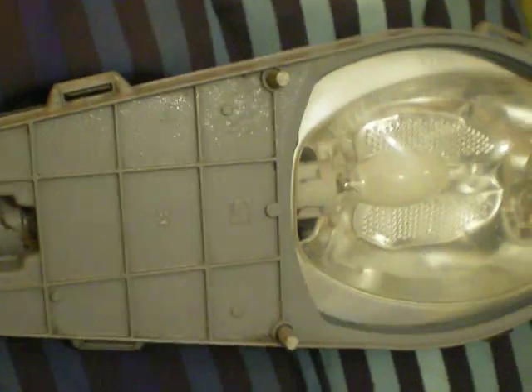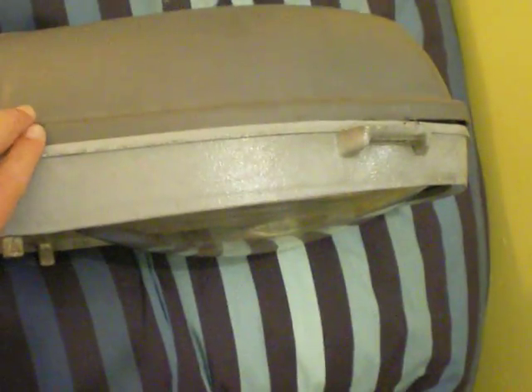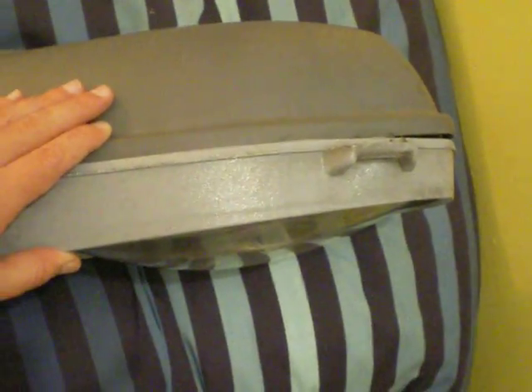So to change the bulb, you don't have to turn the fitting around. The engineers just remove the roof — the top bit. This is where the actual post would go in. You have a set of allen keys, undo these screws, put the metal rod through there, then do them up nice and tight and it's fixed. It's a sealed lens and it has to meet modern light pollution requirements. Your new light fittings now have to have flat lenses to prevent sky glow at night time.